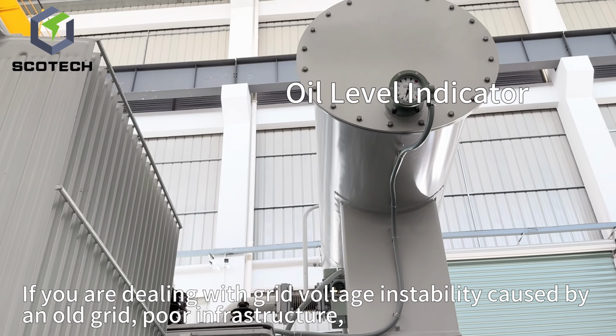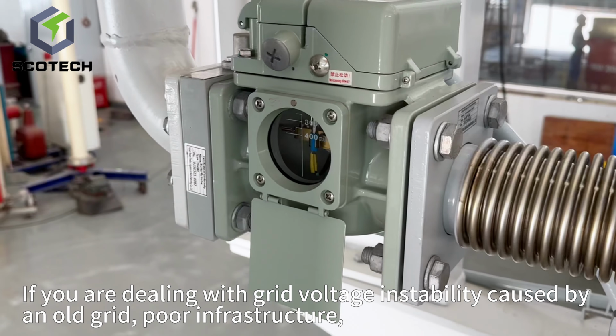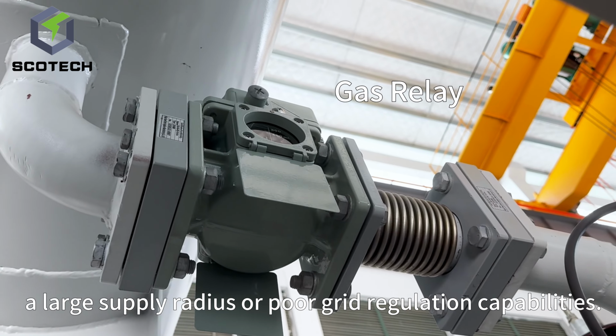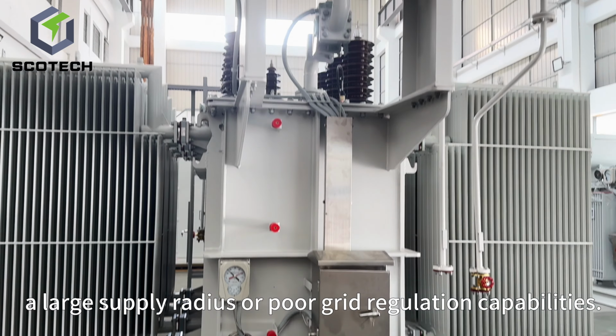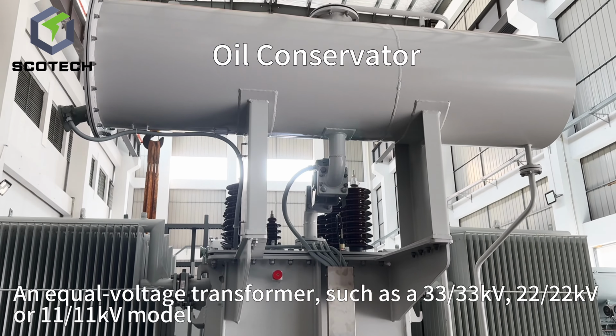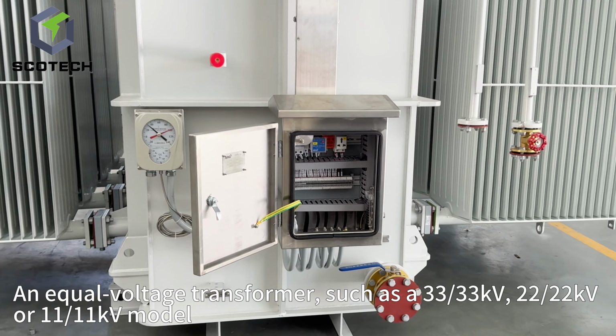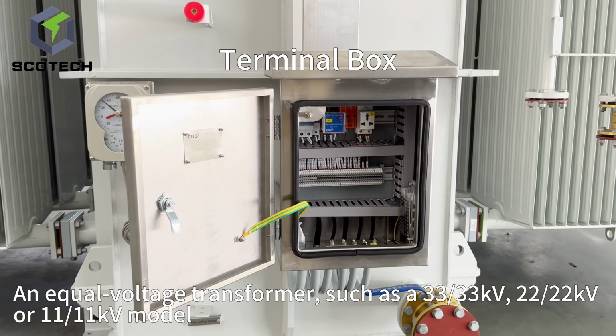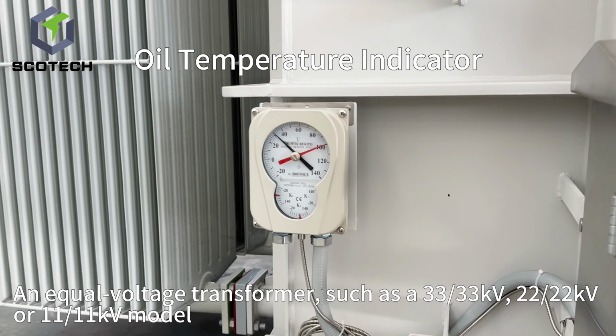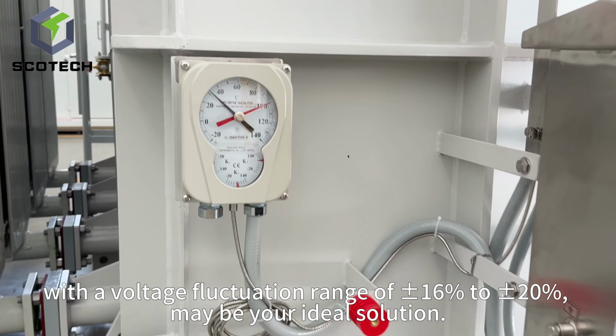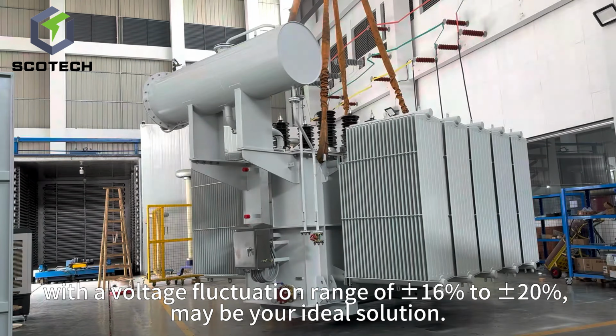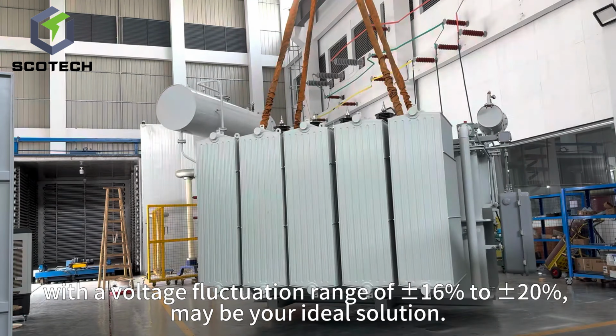If you are dealing with grid voltage instability caused by an old grid, poor infrastructure, a large supply radius, or poor grid regulation capabilities, an equal voltage transformer, such as a 33 kV, 22 kV, or 11 kV model with a voltage fluctuation range of plus or minus 16% to plus or minus 20%, may be your ideal solution.